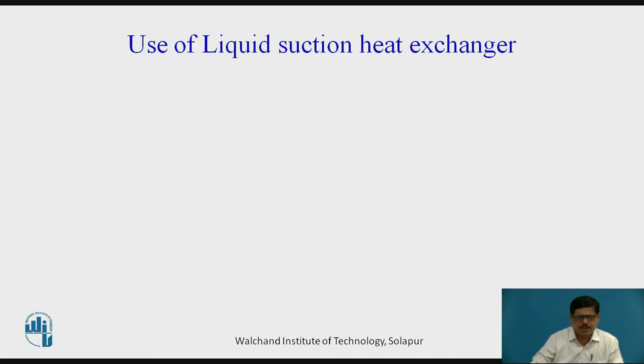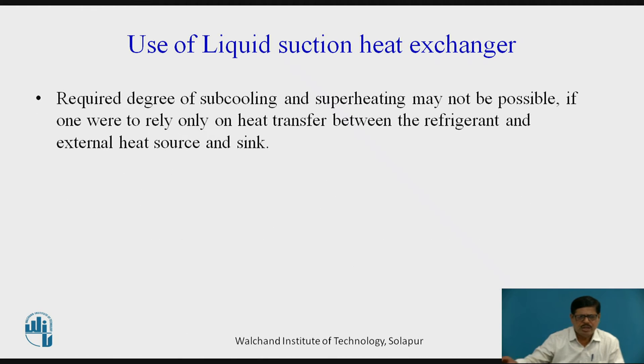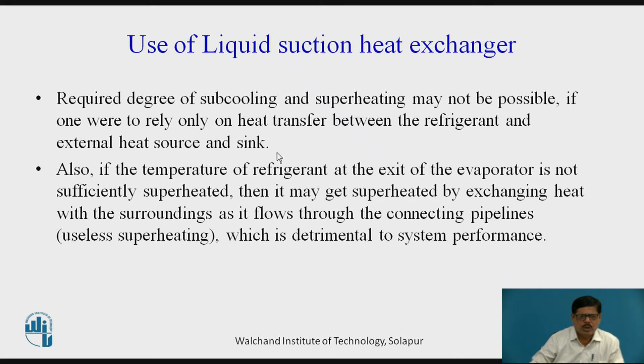Now let us discuss an interesting device — the liquid suction heat exchanger. If you want to achieve both subcooling and superheating simultaneously, then we can use the liquid suction heat exchanger. The required degree of subcooling and superheating may not be possible if we rely only on heat transfer between the refrigerant and external heat source and sink. Therefore, if the temperature of refrigerant at the exit of the evaporator is not sufficiently superheated, it may get superheated by exchanging heat with the surroundings as it flows through the connecting pipelines — which is useless superheating and therefore detrimental to system performance.